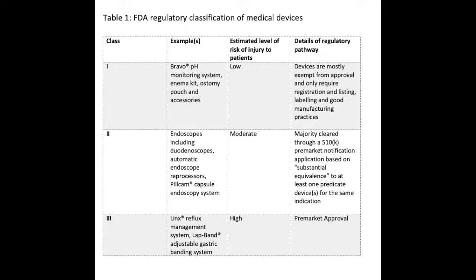These devices are cleared through the 510(k) pathway, also called pre-market notification. Manufacturers must establish substantial equivalence of a new medical device to an existing device, the so-called predicate device, for the same intended use that has received prior FDA approval. The 510(k) pathway is the most commonly used pre-market review pathway for medical devices.